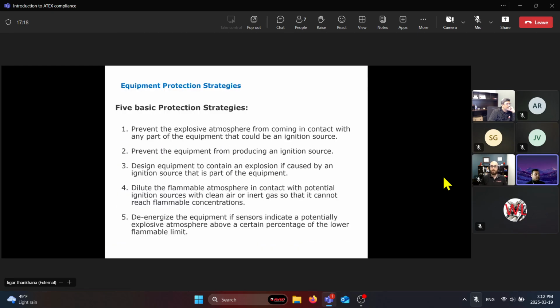So these are some of the basic protection strategies: preventing any explosive atmosphere from coming into contact with any part of the equipment that could be an ignition source, preventing the equipment from producing an ignition source itself, and designing equipment to contain an explosion if caused by an ignition source that is part of the equipment. This would fall under a flame-proof enclosure, for example. Then there is diluting the flammable atmosphere, and de-energizing the equipment. These are some of the most basic strategies used out in the market, just so you have an idea. If anyone has any questions, please feel free to jump in.